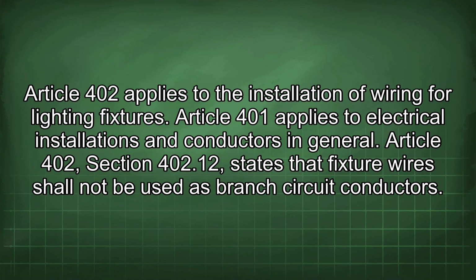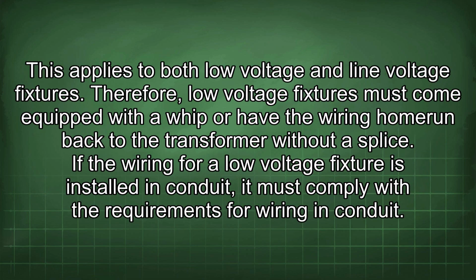Article 402 applies to the installation of wiring for lighting fixtures. Article 401 applies to electrical installations and conductors in general. Article 402, Section 402.12 states that fixture wires shall not be used as branch circuit conductors. This applies to both low voltage and line voltage fixtures.